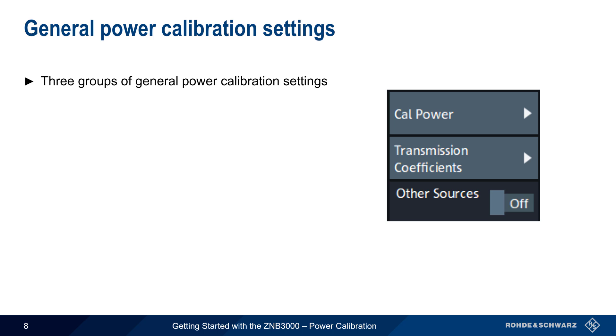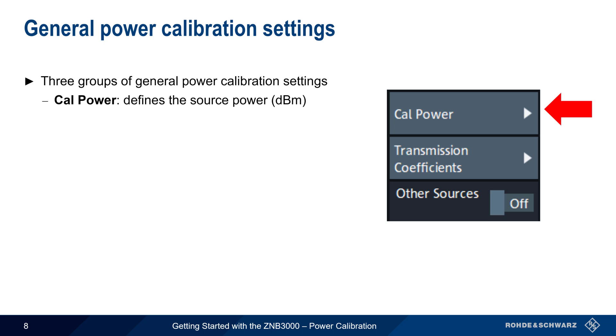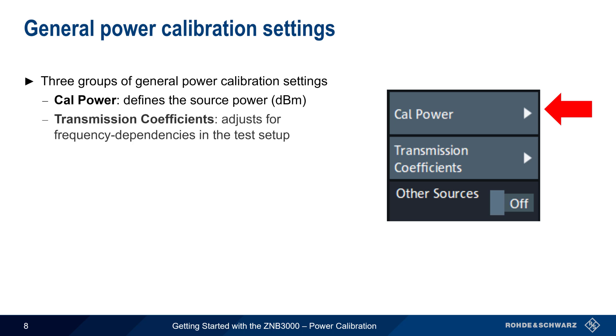Under the General Power Calibration Settings, the most important setting is Calibration Power, which defines the source power in dBm. The Transmission Coefficient Settings are used to compensate or adjust for frequency-dependent behavior of devices in the test setup. The Switch Off Other Sources checkbox is used to ensure that only the calibrated source is on during calibration.